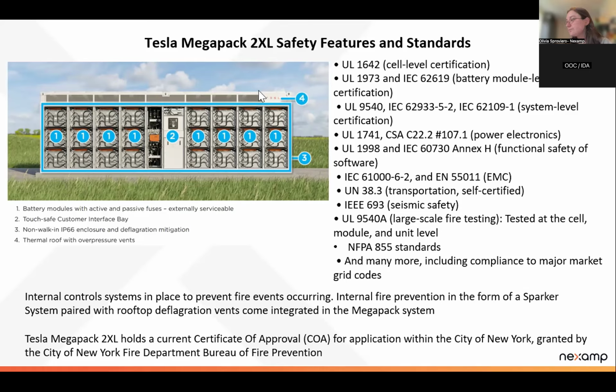Is there any on-site fire suppression built in? It's really just the sparker system that prevents it from having any explosion that would lead to exposure from the outside. But it's been tested whether foams, aerosols, or water do any helpful suppression, and for these types of batteries, they really don't. They end up causing more of an issue.